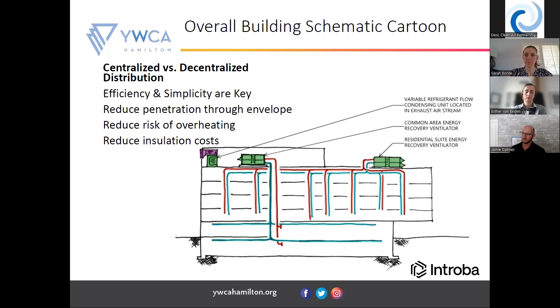So we're tightening the ducts here. There are other strategies that maybe got looked at for future projects. Here we only used the ERVs to do the energy exchange. As Esther was saying, they're desiccant dehumidification wheels, and they only do energy exchange, then the dehumidification happens inside the suites at a terminal fan coil. Every suite has its own fan coil unit. That does mean we used insulated ductwork throughout the building.